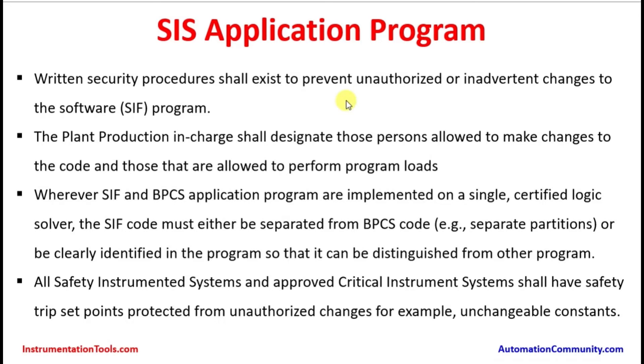Written security procedures shall exist to prevent unauthorized or inadvertent changes in the software program. Only experienced personnel who are familiar with and have experience on the safety instrumented system, and who are certified to work on the particular area, can make modifications — not persons who belong to a different plant area. Even if knowledgeable, a person may not have certification to work on a different plant. For example, an engineer from Plant A cannot directly work in Plant B. In cases of emergency where the Plant B engineer is unavailable, based on manager approval, the person from Plant A may come and work in Plant B.